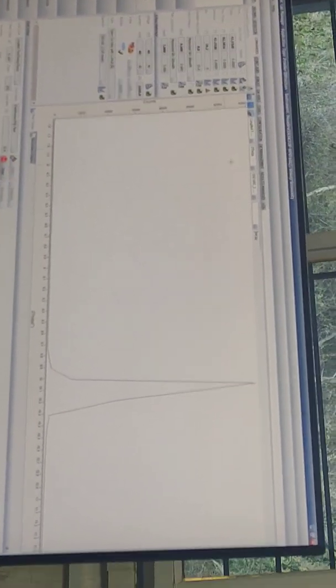and then you will do the measurement again and see how many data points I am getting. You have to optimize this thing. Every time, 6 to 9 data points have to be there for the highest peak in your XRD pattern. Then only you can use this data for Rietveld refinement. If I use the previous data for Rietveld refinement, the results are definitely not correct. You should not use this. It's the biggest blunder we are making. We should never do that.